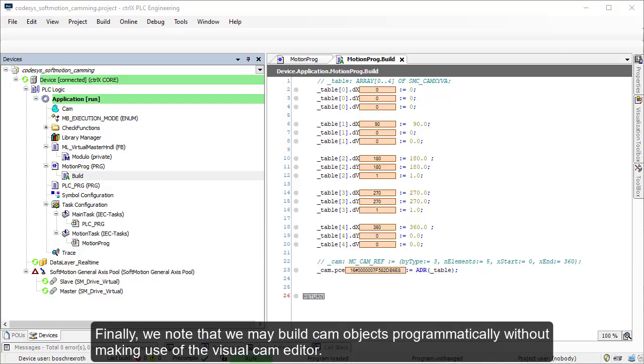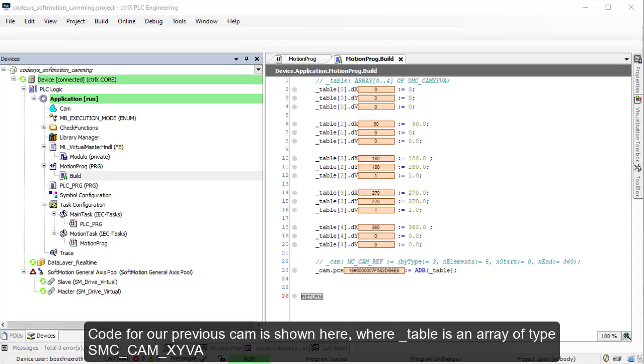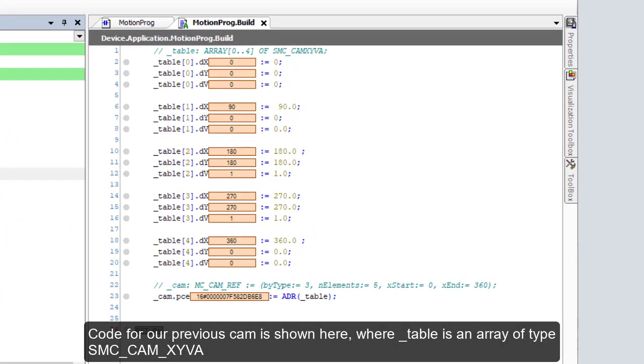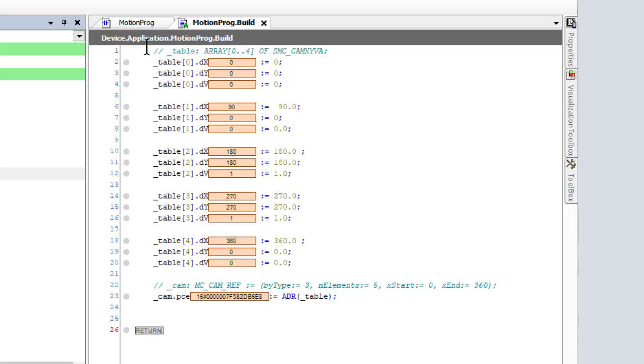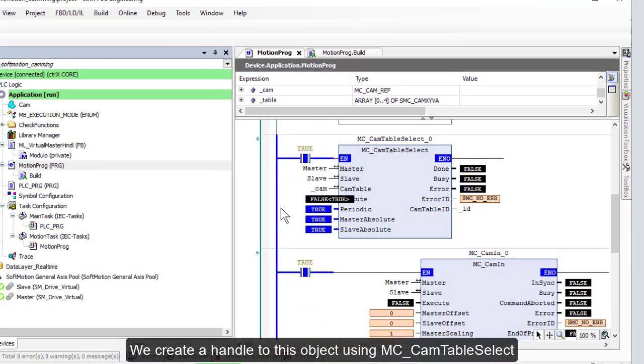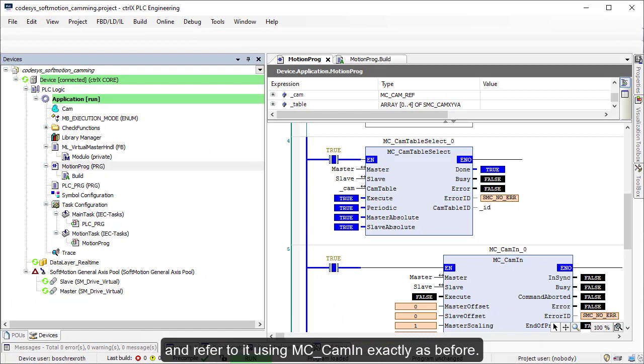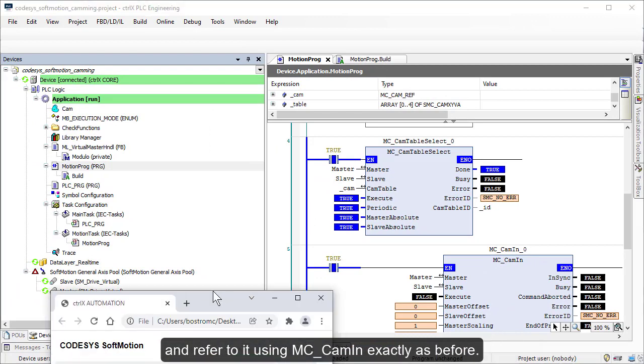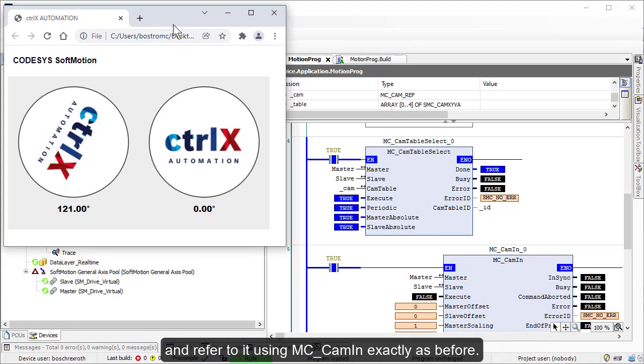Finally, we note that we may build cam objects programmatically. Code for our previous cam is shown here, where table is an array of type SMC_CamXYVA, and our cam object, CAM, is of type MC_CamRef. We create a handle to this object using MC_CamTableSelect and refer to it using MC_CamIn, exactly as before.